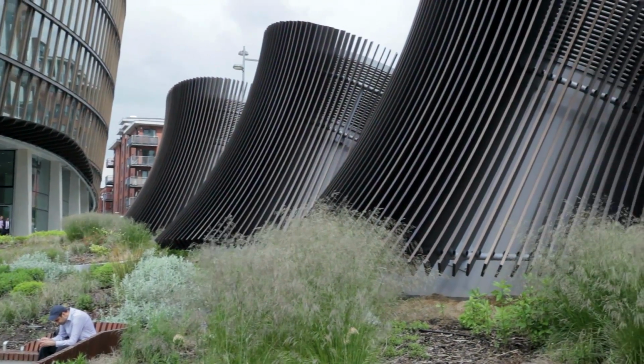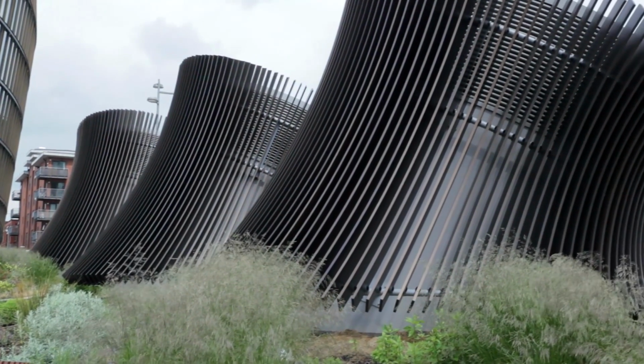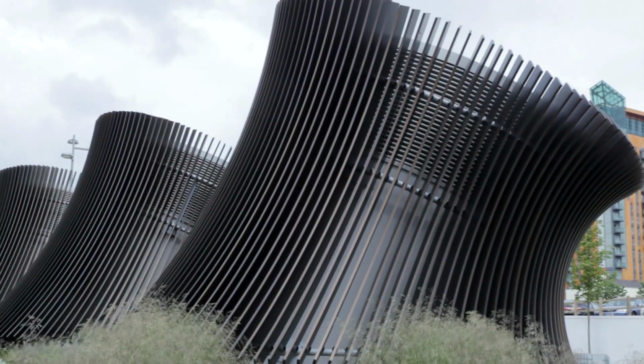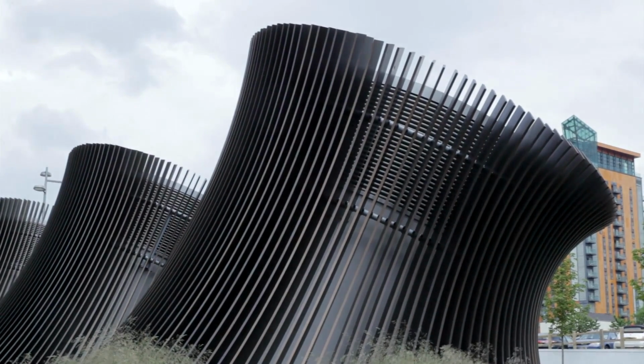And the reason why they're effective in what they do is because the temperature of the ground is a relatively stable 12 degrees, roughly, give or take, throughout the year. And what they do is they draw air in through the ground and work as giant heat exchangers. So they preheat the air coming into the building, or pre-cool it in summer. And what they do is they just add a little bit of temperature modulation. They don't do all of it, but they do some of it. And on a building of this scale, it does make quite a large difference.